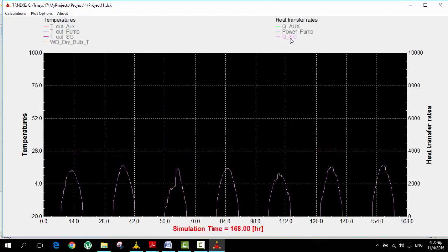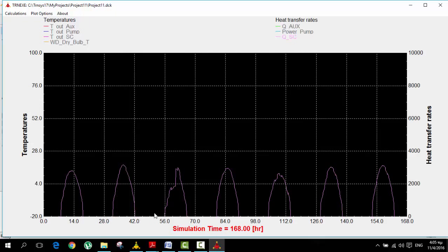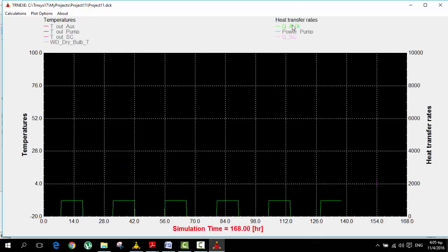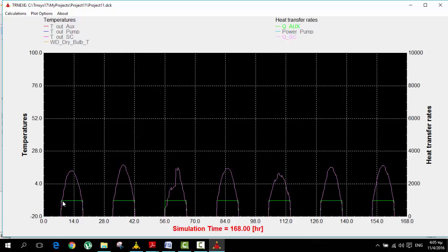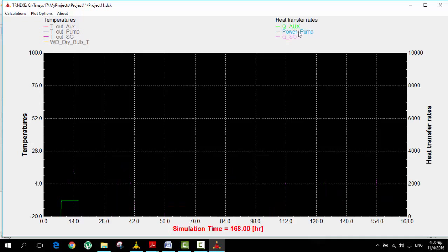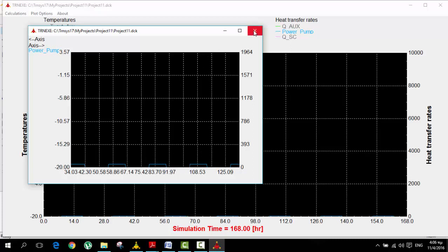Here is the dry bulb temperature. And then here we can see the energy that we get from the solar collector, which is kind of normal because this is the time of the day. Here we see the energy from the auxiliary heating, and this is the power of the pump. It's not shown very well. The pump is working only in this situation, so during the night the pump doesn't work because there is no need for that.